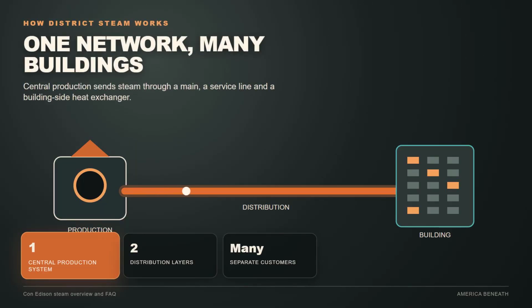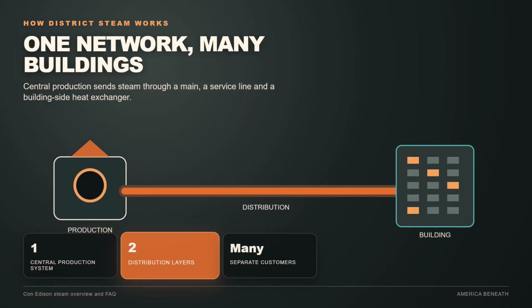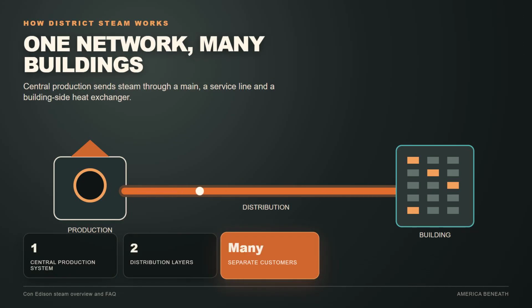Start with the basic transaction. A generating plant heats treated water and produces steam. Pressure moves that steam through large underground mains. Smaller service pipes branch from those mains and enter customer buildings. Inside, the steam reaches equipment that transfers its energy into the systems people actually use. The network is the delivery system. The building still controls what happens after the connection.